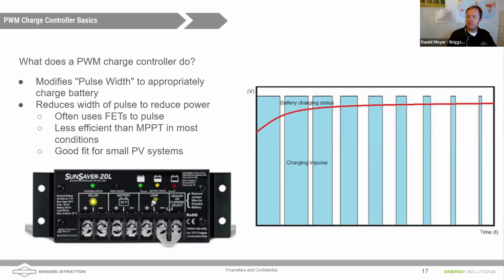When I worked at Sunfrost, the refrigeration company, and we did vaccine refrigerators, we would often use these. That was maybe 15, 20 years ago. Really the MPPT charge controllers have become much less expensive. Also, by using PWM, you really need to use either 36 or 72 cell modules to get close to that voltage range of what the batteries are.